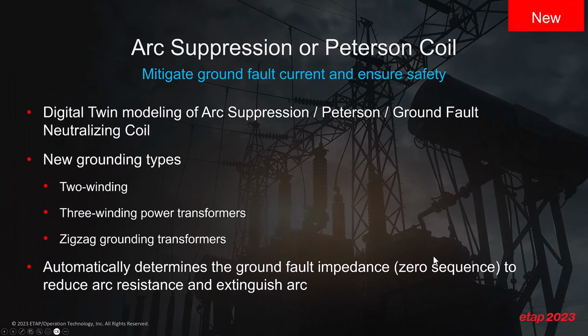The arc suppression or Peterson coil can therefore be used for 2-winding transformers, 3-winding transformers, zigzag grounding transformers, and then it's able to automatically determine the ground fault impedance, the zero sequence that is needed to reduce the arc resistance and of course ultimately extinguish the arc itself.